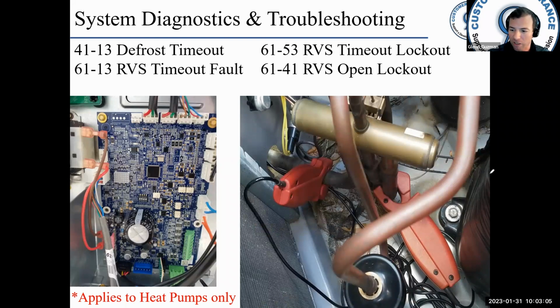Okay, you see this is not a variable speed unit here on the right, but it's a reversing valve, and troubleshooting a reversing valve is the same no matter what unit you're in. So you want to check whether you're in heating or cooling. In this case, if I'm cooling, this would be my suction line. I'm sorry, this is actually troubleshooting heating. So this is my discharge line, and this is going to my coil. I'm sorry, I misspoke again. Trying to go a little too fast here.